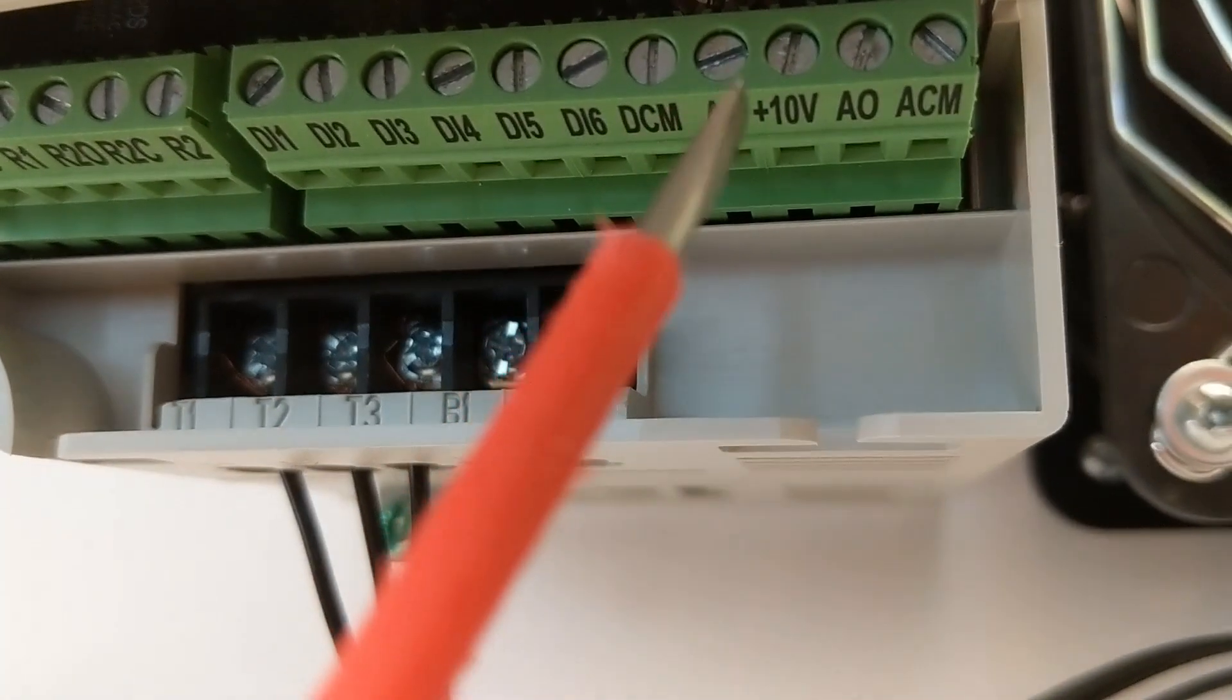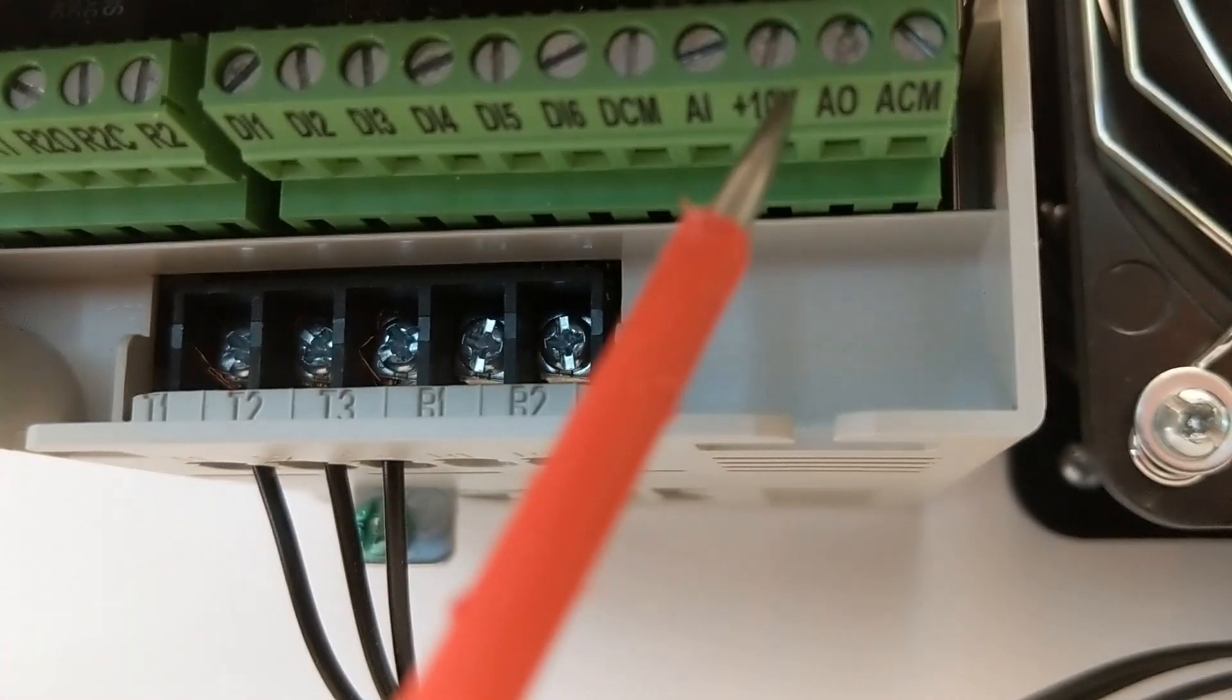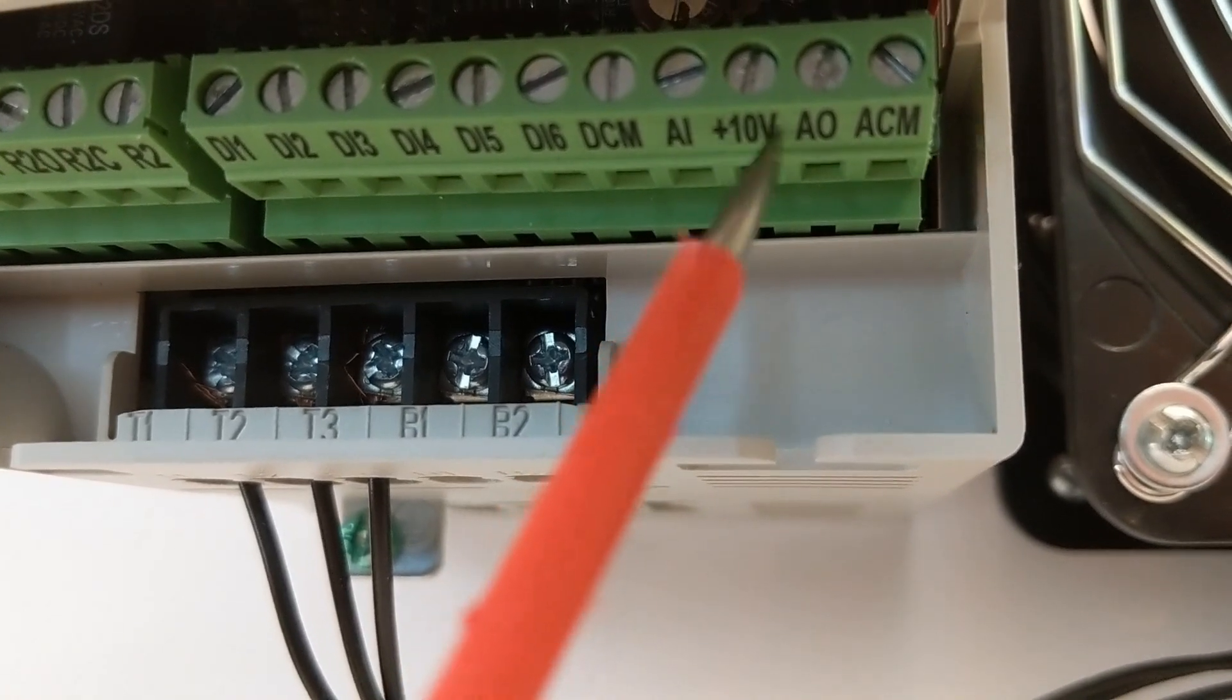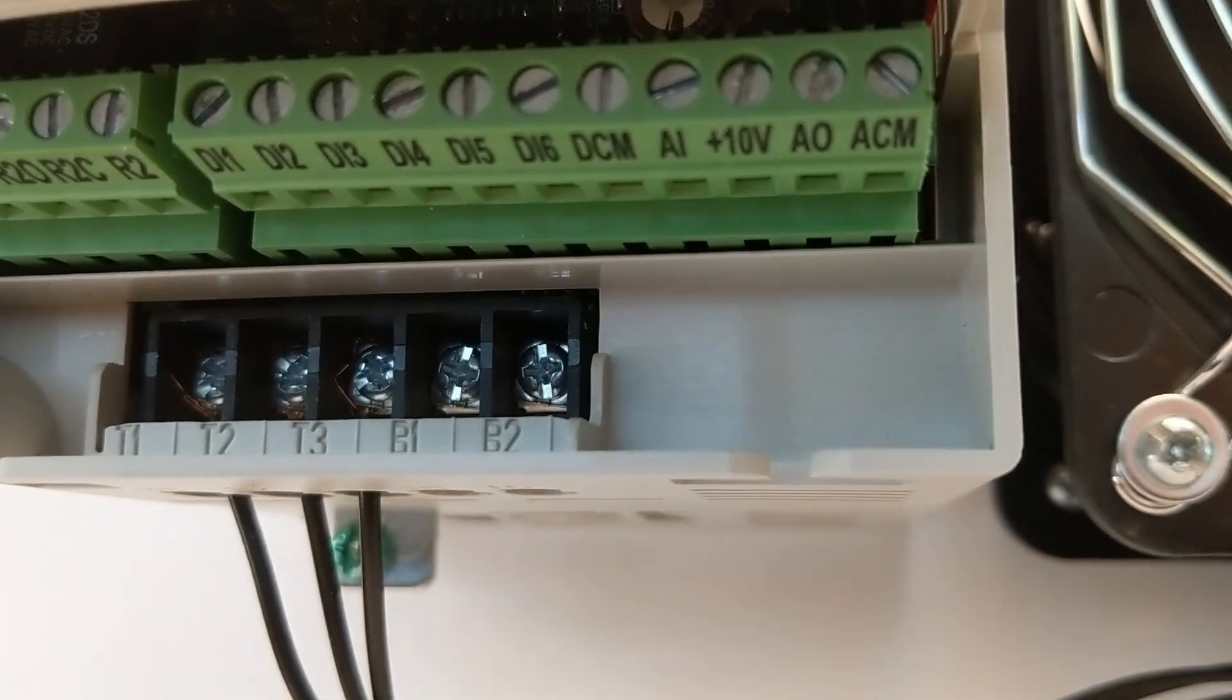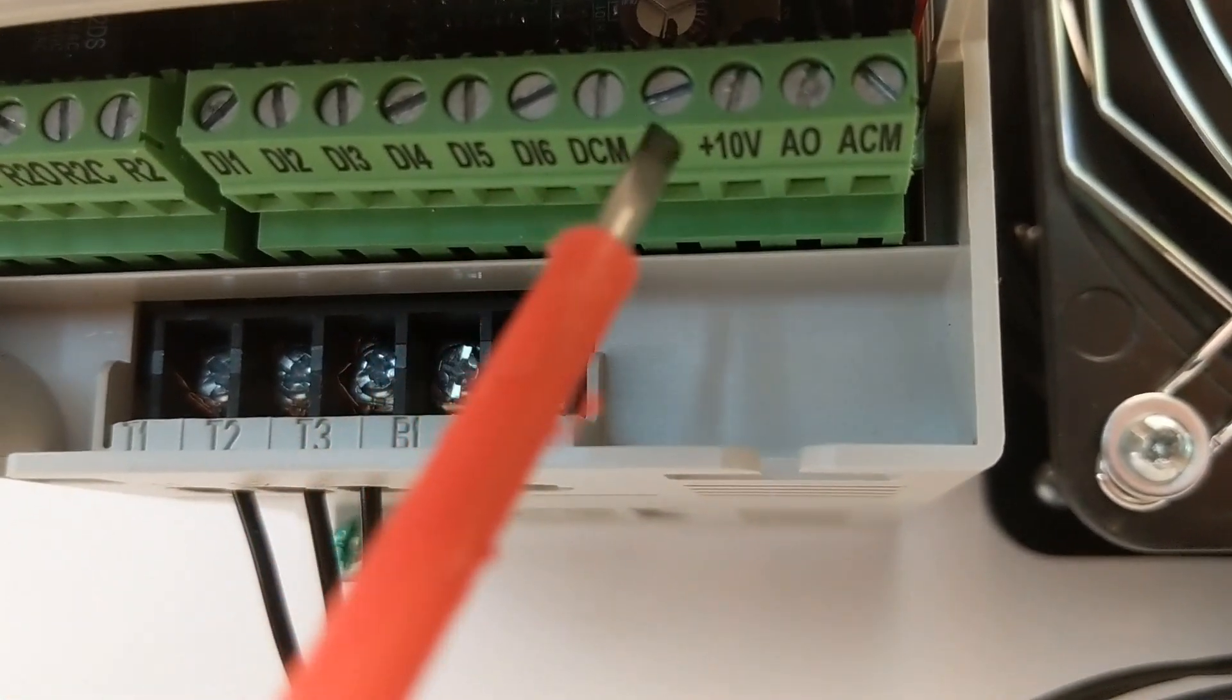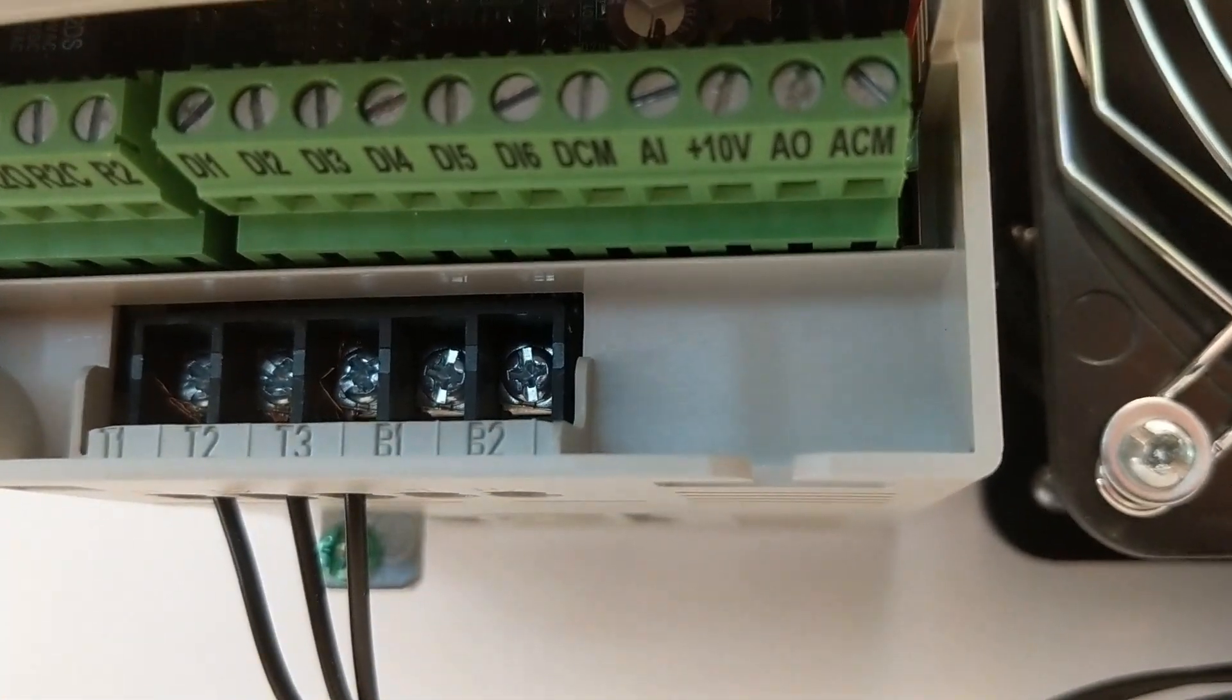So right here you can see we have our analog input to our drive, but right beside it we have a plus 10 volt and our analog common. So right there we can pick up 10 volt and normally that potentiometer would go back to this analog input.